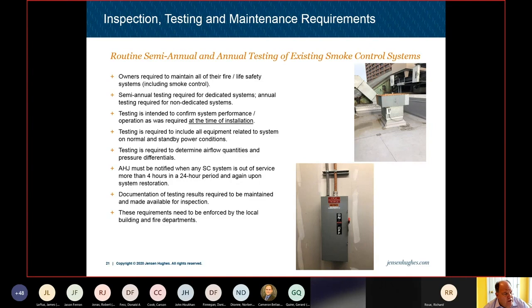But there's some other nuances. We're not only testing some inputs and outputs, but we need to also test this stuff on normal and standby power. So we're talking about emergency generator power tests, which kind of drive owners crazy. They don't like testing their occupied buildings on emergency generator. But that is required even for the semi-annual test. So every 6 months that's supposed to be occurring.